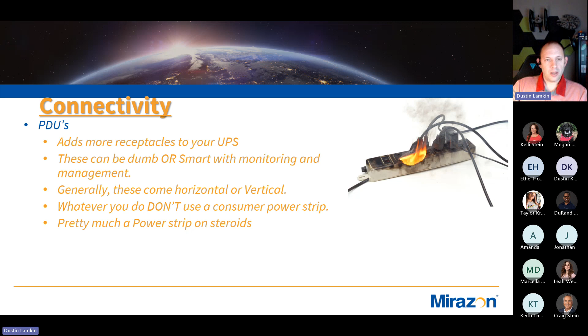These vertical PDUs, while built more for server racks, still have ratings on them—they can be overloaded. There'll be a bank of 6 on the bottom, 6 on the top, however it's built. You can't just plug everything into one bank and call it good. We need to distribute that load evenly, monitor it, and make sure we're not overloading it. Even on the non-network-connectivity PDUs, there's usually an amperage load indicator on the side so you can see what the draw is. Monitoring these is key.